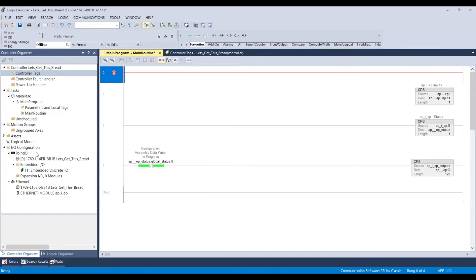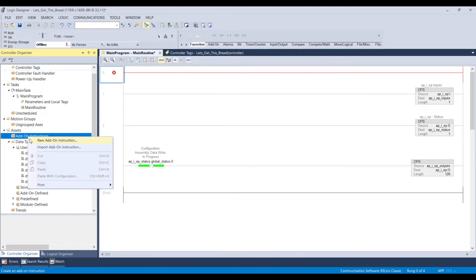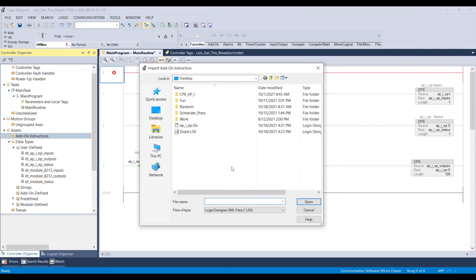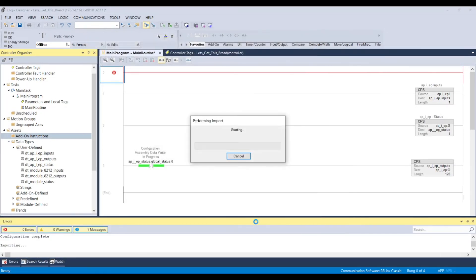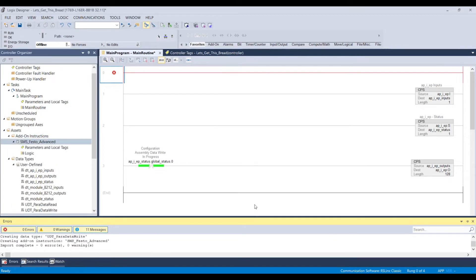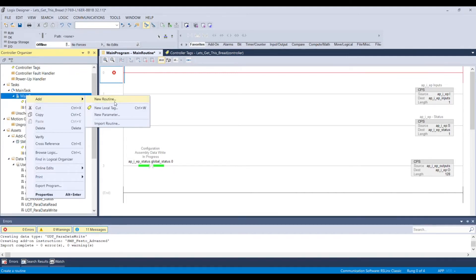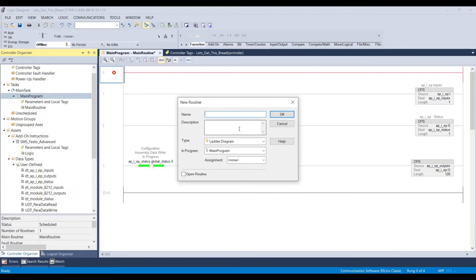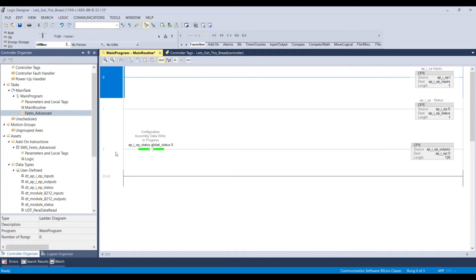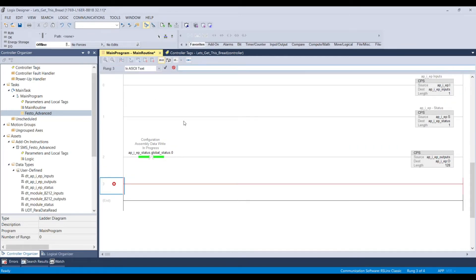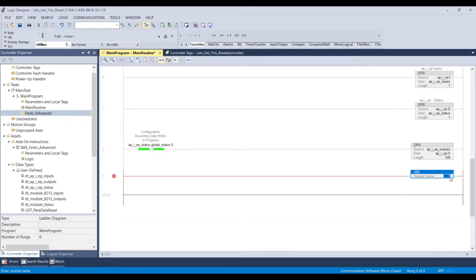The next step is to go to assets, then Add-On Instructions, and import an add-on instruction. Going into the application notes under my CPX application notes, I'm going to click AOI and select the Festo Advanced. Make sure everything imports OK. Then in the main routine I'm going to add another subroutine and name it Festo Advanced. Before we forget, I'm also going to delete a rung, add another rung, and double-click it to set it to JSR. From there I'm going to tell it to reference our subroutine.